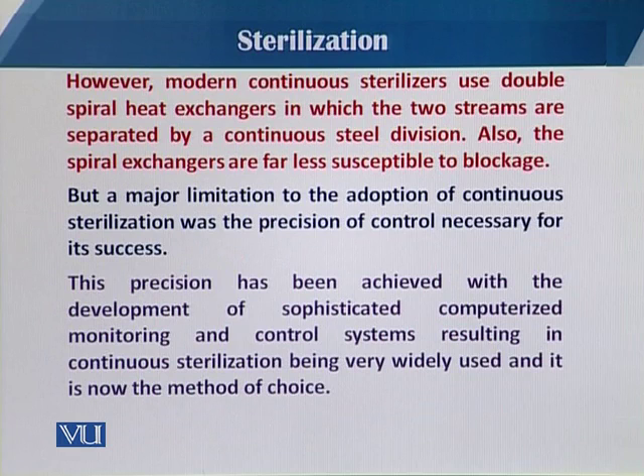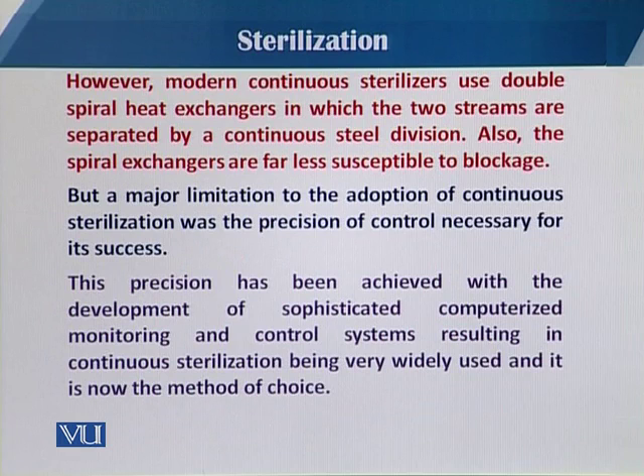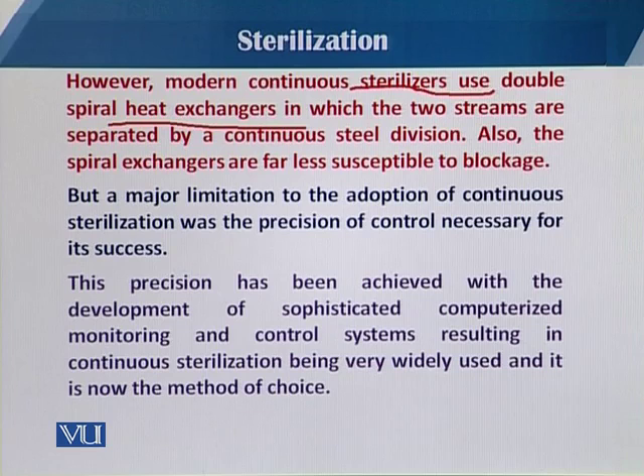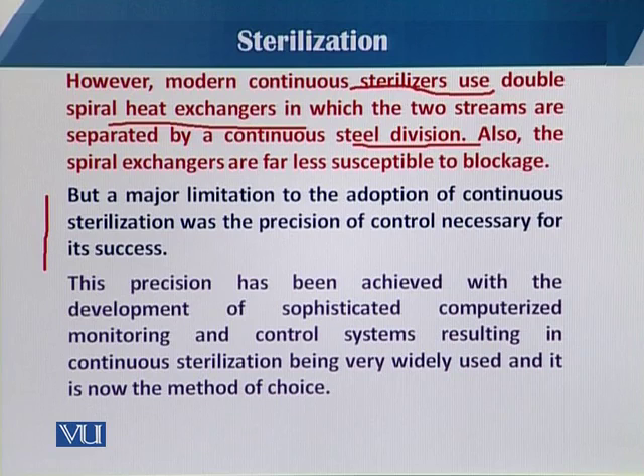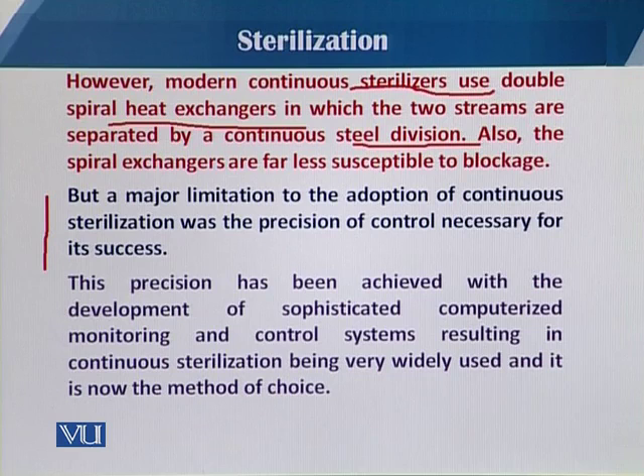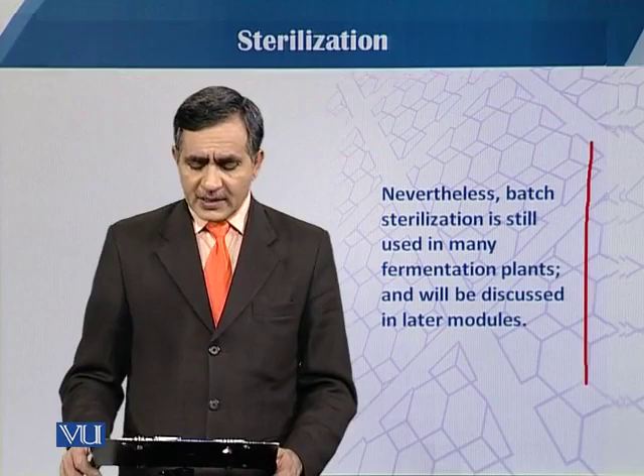Modern continuous sterilizers use double spiral heat exchangers, in which the two streams are separated by continuous steel divisions. The spiral exchangers are far less susceptible to blockage. The major limitation to adopting continuous sterilization was the precision of control necessary for its success. This precision has been achieved with the development of sophisticated computerized monitoring and control systems, resulting in continuous sterilization now being widely used and the method of choice in industrial fermentations.